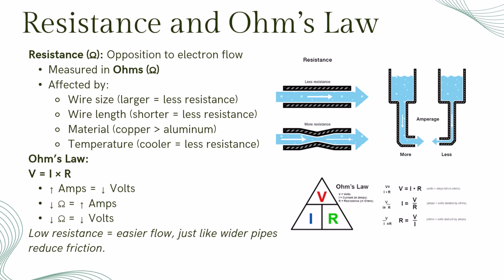The relationship between volts, amps, and ohms is defined by Ohm's law. V equals I times R. So voltage equals current times resistance. When current, amps, increases, voltage tends to drop. This is similar to when larger nozzles are installed. It increases the demand for flow in the pipe, resulting in a lower pressure at the sprinkler head. When resistance or ohms decreases, the amps increase, and as ohms go down, the voltage does too. Understanding this relationship helps you interpret your multimeter readings accurately and diagnose electrical issues quickly.